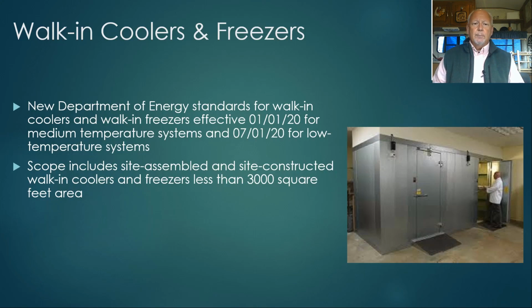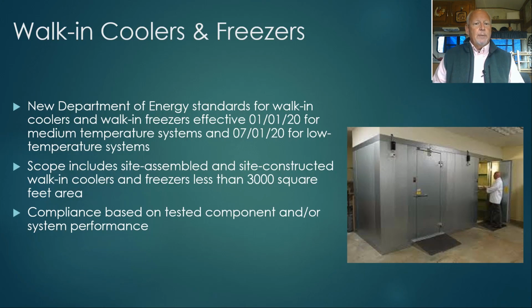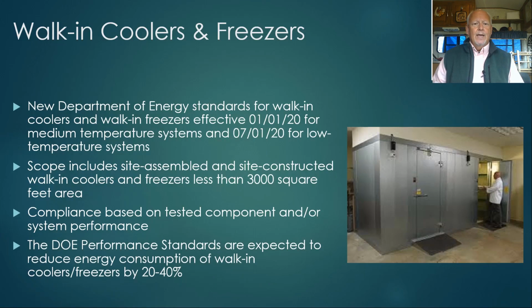The scope includes assembled and site-constructed walk-in coolers and freezers less than 3,000 square feet in area. If you have a walk-in cooler or freezer greater than 3,000 square feet, you would follow the prescriptive requirements in the code. Compliance is based on tested component and/or system performance. This is a general trend in the code where, rather than looking at the performance of individual components, the standard looks at the performance of systems and the components in the system. And these DOE standards are expected to reduce energy consumption of walk-in coolers and freezers by 20 to 40%.